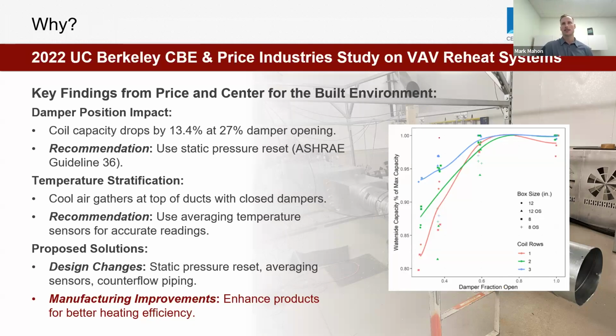The first was, which we can see on the right-hand side of the screen here, they found that coil capacity drops by 13.4% when the damper is only 27% open. So I'll give some more context to that, but let's try to mentally digest that. As the damper shuts, the coil gets worse. So we can see that here on the x-axis, capacity when the damper is 100% open versus capacity when the damper is 0.27. We can see a huge deterioration in coil performance.